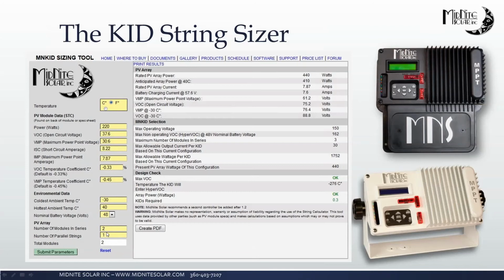These two parameters here are the ones that you're going to play with. You keep putting modules in series and hit your submit parameters and see what it comes up over here and tells you. A lot of good information up top, but in reality, these are the 4 fields down here you're really going to focus on. The max VOC, is it okay? Is it excessive? The temperature, the Kid will go into hypervoc. So if this temperature starts to get down to a number that you see on any regular basis, then you've got too many modules in series, essentially is what this is telling you. So then we want to go back over on the left-hand side and we want to rearrange that and keep playing with it. And we want to get that to the point where these numbers, this is all green and this number looks good. These last two, the wattage and the number of Kids required, just like on the Classic, the Kid can be what we call overdriven or over PV'd.